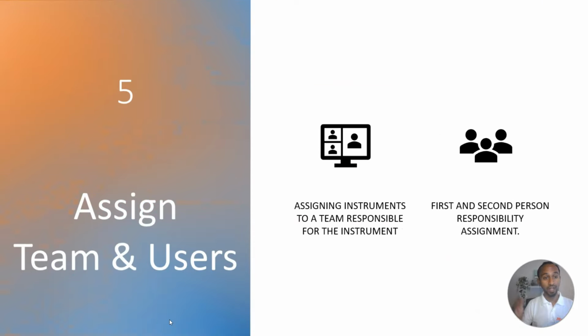Number 5. Assign team and assign users for specific instruments. So here you can assign the instruments to a specific team. This could be your internal team or your external team, like your vendors who are responsible for calibrating the instruments, or you can even assign any specific person internally in your organization or externally who has to look after that.